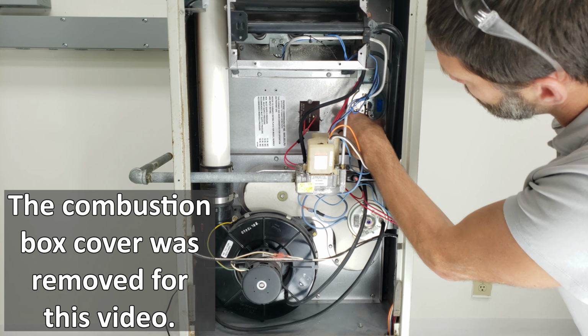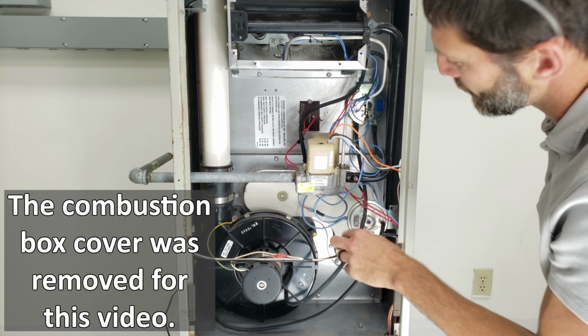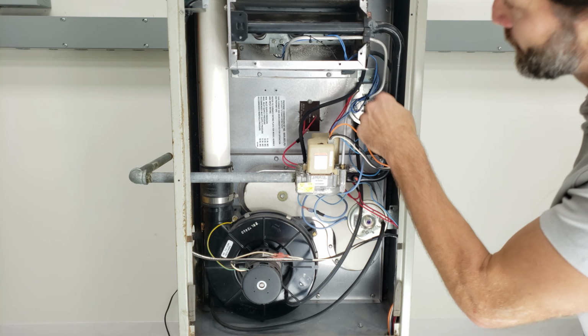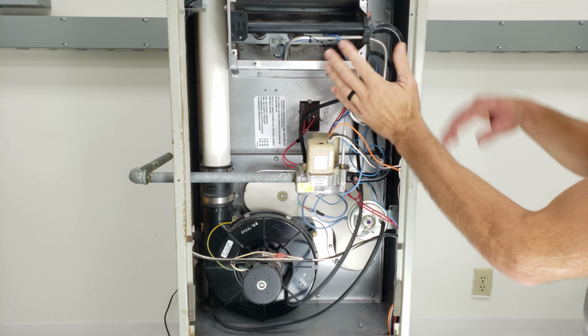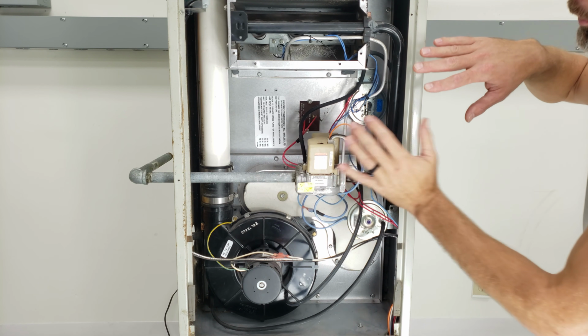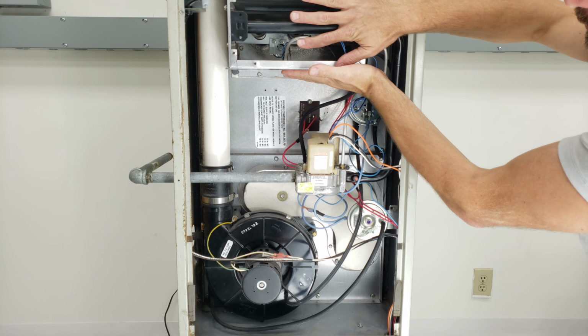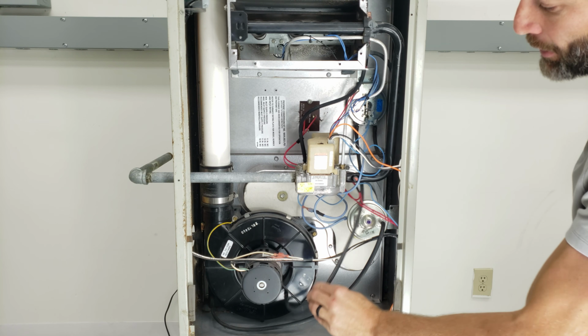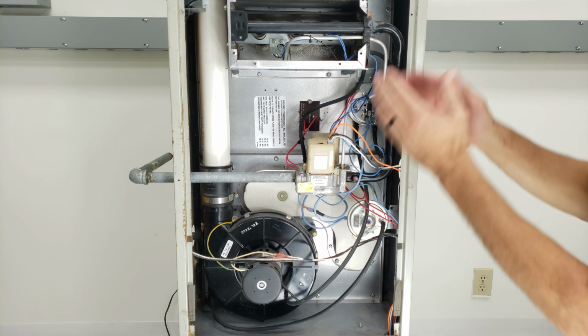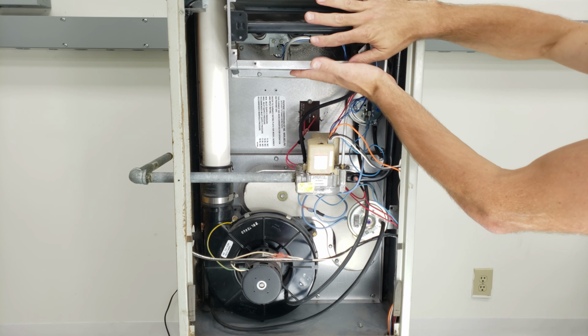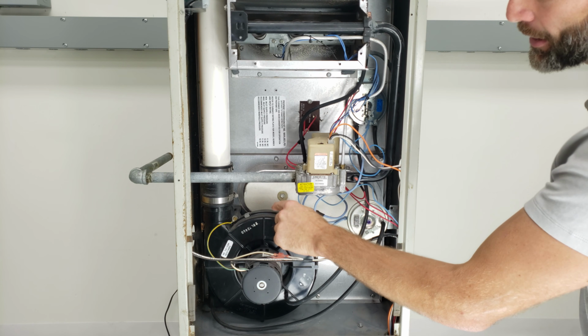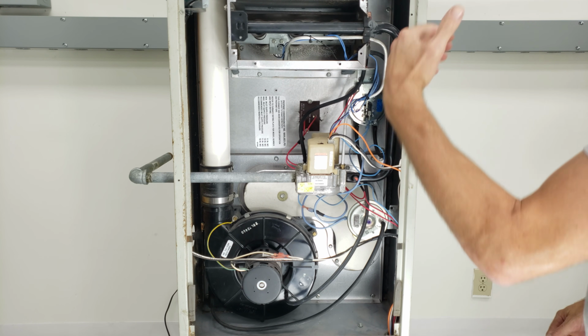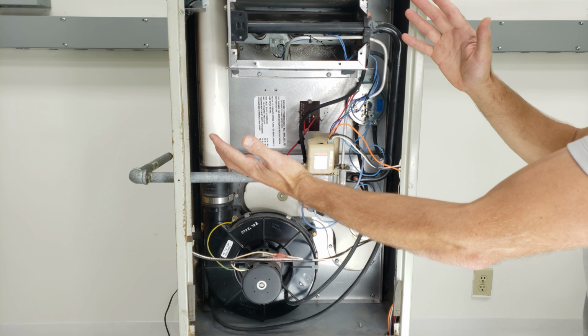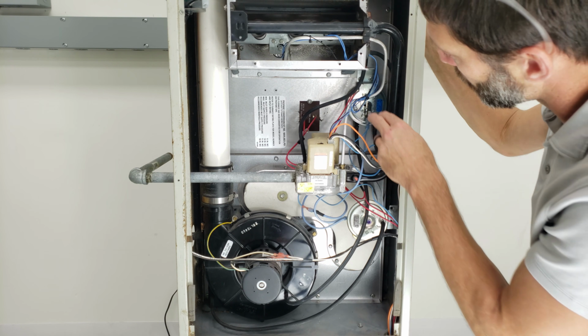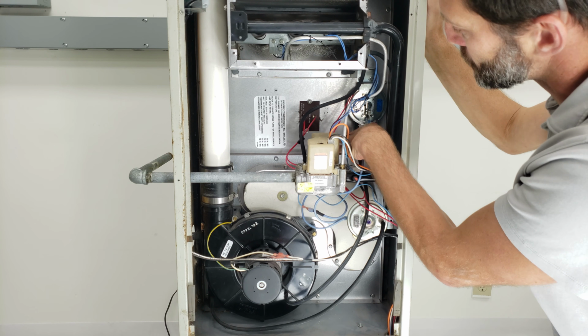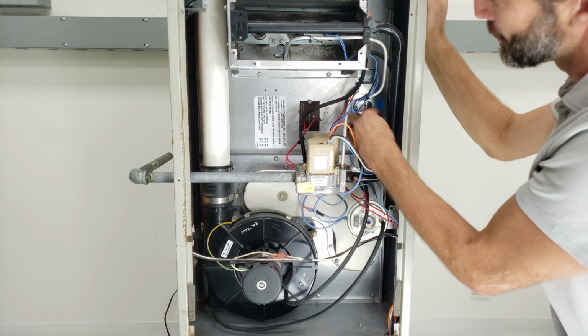But right here, this pressure switch has a negative, and the negative is connected to the inducer motor, and the positive is connected to this box. So while the system's running, while the inducer motor is running, this box is going to be lower than atmospheric pressure, but the pressure over at the inducer motor is going to be reduced lower than what's in this box right here because of the distance, because you have a heat exchanger between here and here. In fact, you have two heat exchangers because this is a 90% efficient furnace. And so now we're going to hook up our water column manometer, and we're going to measure the differential between the negative and the positive port of this switch.